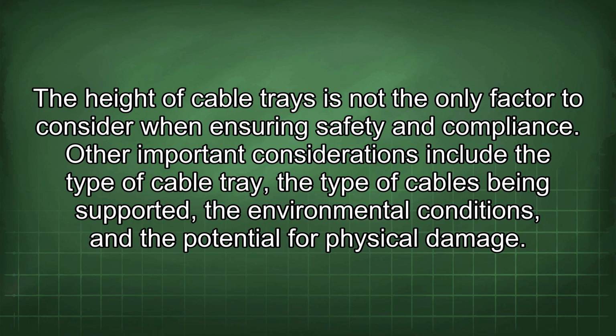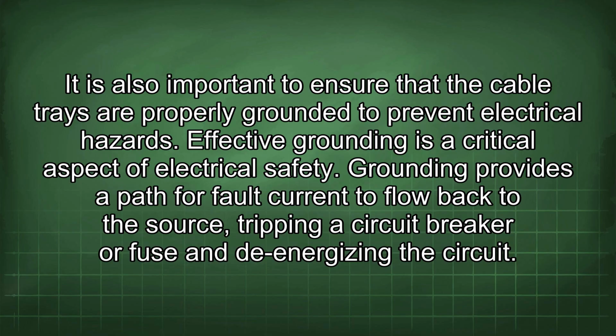The height of cable trays is not the only factor to consider when ensuring safety and compliance. Other important considerations include the type of cable tray, the type of cables being supported, the environmental conditions, and the potential for physical damage. It is also important to ensure that the cable trays are properly grounded to prevent electrical hazards. Effective grounding is a critical aspect of electrical safety.